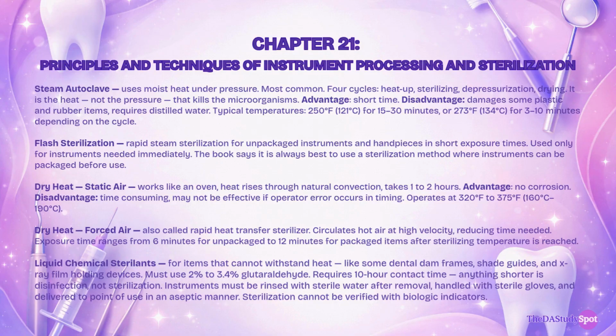Next, we have dry heat static air. This works like an oven. Heat rises through natural convection and takes 1 to 2 hours. The advantage, no corrosion. The disadvantage, it is time consuming and it may not be effective if operator error occurs in timing. This operates between 320 to 375 degrees Fahrenheit. Next is the dry heat forced air, also called rapid heat transfer sterilizer. This circulates hot air at a high velocity, reducing time needed. Exposure time ranges from 6 minutes for unpackaged to 12 minutes for packaged items after sterilization temperature is reached.